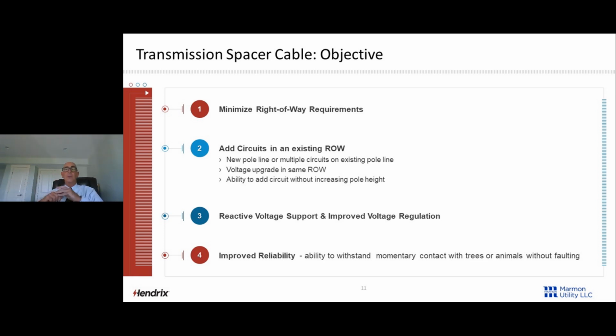What are our objectives? Why do we want transmission spacer cable? What are the motivating factors? Well, first of all, we want to minimize our right-of-way requirements. We want to have the ability to add circuits in an existing right-of-way. Maybe put a new pole line or multiple circuits on an existing pole line. Maybe we're going to use a voltage upgrade in that same right-of-way. We've got a 15, 25, 35 kV right-of-way. Maybe convert that to 69 with a 15 kV below. And the ability to add a circuit without increasing pole height. And we'll see how this goes.